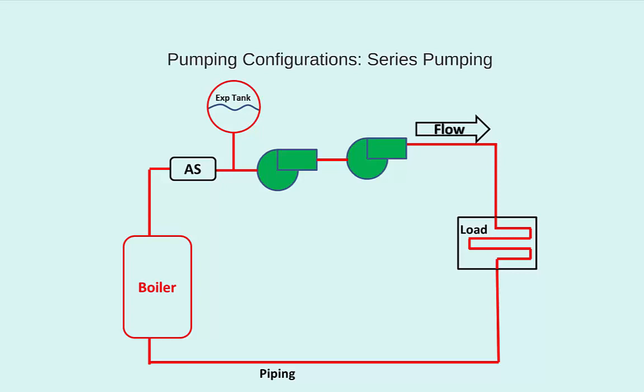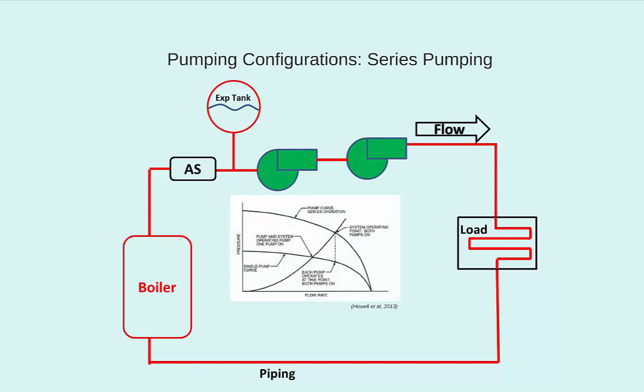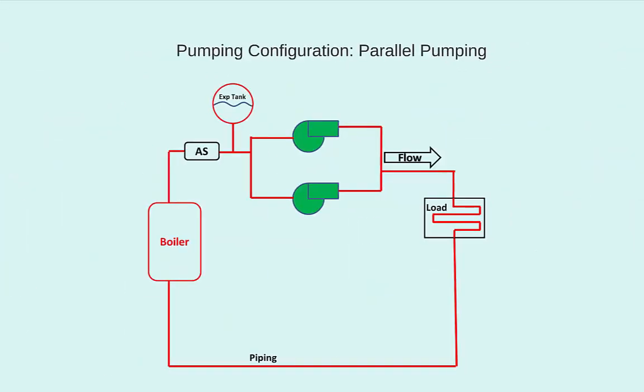Nevertheless, when pumps are used in series, the effective pump curve with the system curve overlaid on it looks like this. It is important to note that when pumping in series, each pump sees the same flow rate, but they both add pressure into the system. More commonly, we see a second pump piped in parallel. This is often done where both pumps are sized to push the entire system's flow requirements. They are fully redundant and never operate at the same time.